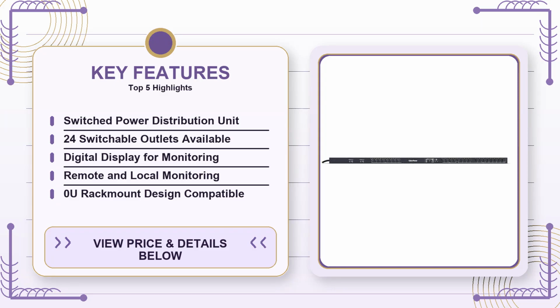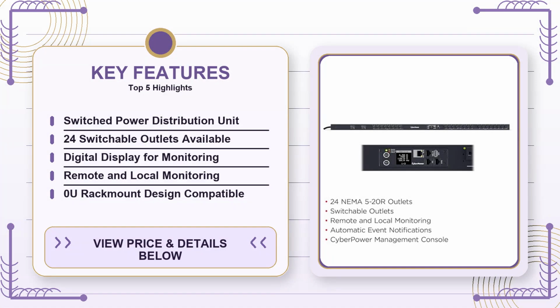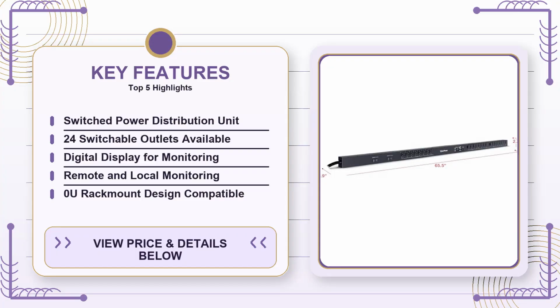The unit also offers a decent amount of flexibility in outlet placement. All 24 outlets are arranged in a single row, which makes cable routing simple and predictable. You won't have to deal with a tangled mess of staggered sockets where a thick power cord blocks neighboring outlets, a common annoyance with some older PDUs. This straight-line layout works well with standard 18-inch rack depth setups and allows you to neatly route cords to the back of the rack, keeping the front clear for visual checks.